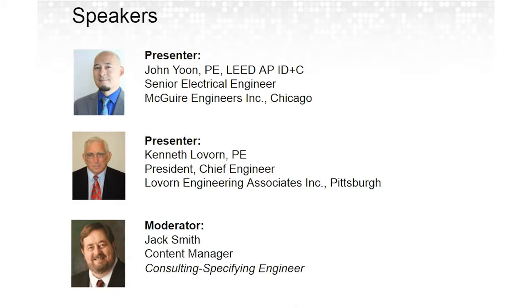The second part of it is inverter duty rated motor. So what we're talking about is not power quality for the rest of the facility. What we're talking about is the ability to have a long life motor that isn't going to fail immediately. So what do we do to mitigate any type of issues like EDM or anything else that might cause damage and reduce life expectancy for that motor? And again, we have multiple different things that we can do. We can armor plate the motor and specify a NEMA MG1 Part 31 motor, but you can also do things to sort of mitigate the chance of that EDM.